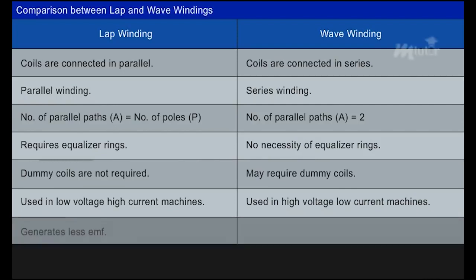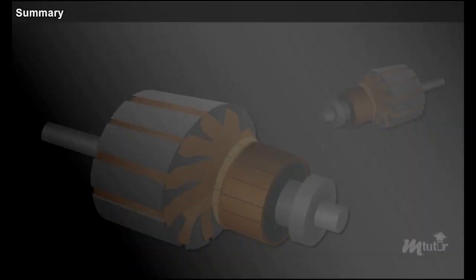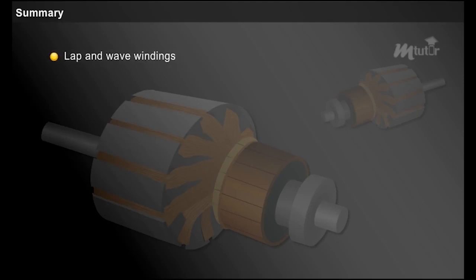Lap winding generates less EMF compared to wave winding. Due to more parallel paths, lap windings can be used for large-current applications, whereas wave winding is not suitable for such applications as it has only two parallel paths. This brings us to the end of the lesson, in which we have learned about lap and wave windings, equalizer rings, and dummy coils.